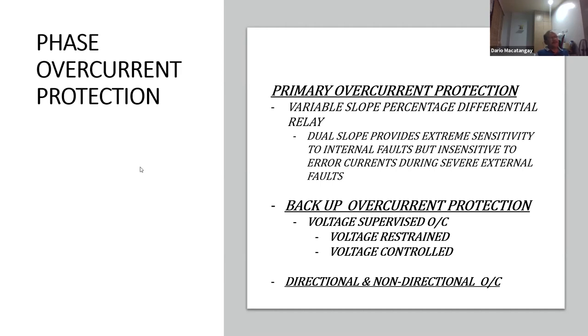Now, let's say the fault is on the generator step-up transformer. It's not covered by the zone of protection. Therefore, if there's a fault on the transformer, that is considered an external fault. And if it is an external fault, the transformer differential should trip, but not the generator protection. So that's one thing good here with the variable slope. It provides extreme sensitivity for internal faults, but insensitivity to error currents during severe external faults.